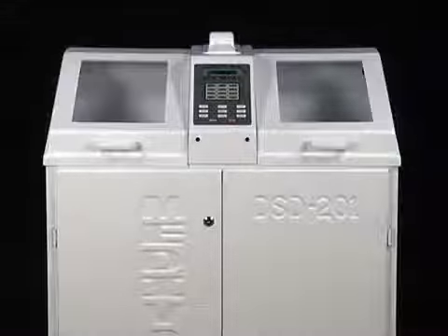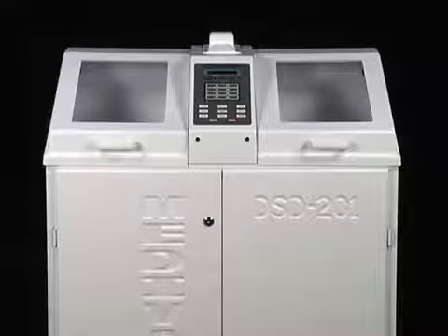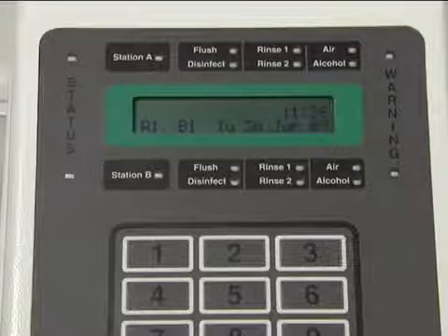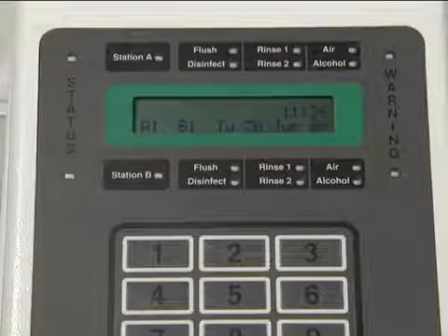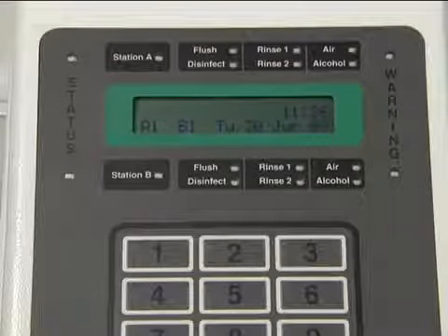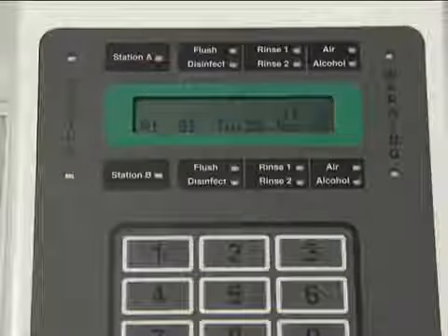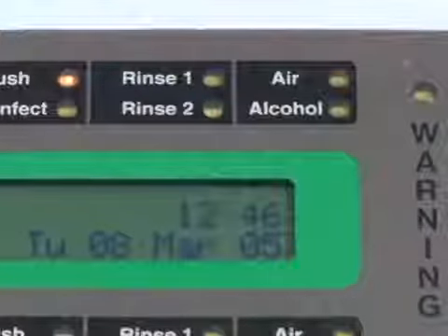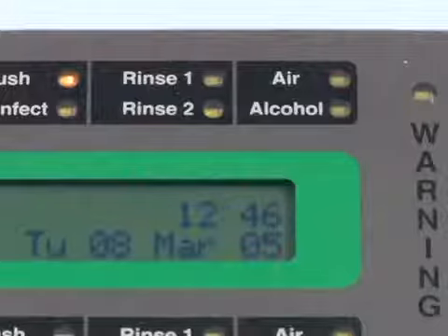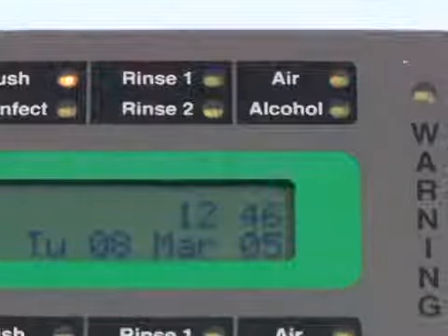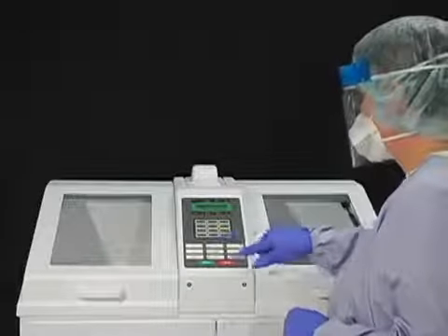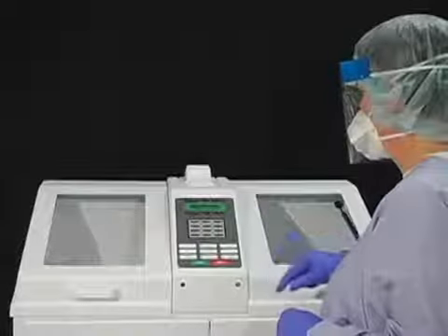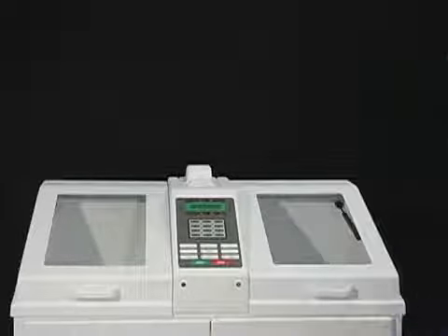The duration of the DSD-201 cycle depends on the parameters that have been entered. We will discuss programming custom parameters in Section 9. The LEDs in the station status and warning section indicate which phase of the cycle is currently in progress. The air light will flash at the end of each cycle phase to indicate channel purging. The remainder of the disinfection process is fully automated. No further operator attention is required.